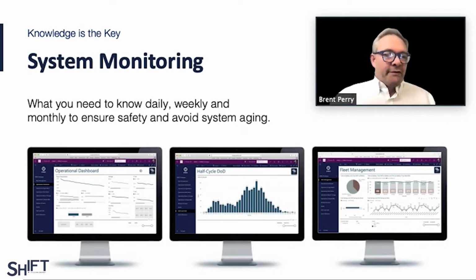We can do that today with a lot of very sophisticated but usable software. In our case, we monitor the cells at the cell level, no matter how large the system is, and it's that management at the cell level that effectively allows us to proactively prevent fire from occurring. This management system, though, has to be enabled to be operating continuously. You may not be using the energy storage, you may have turned it off, but because a lithium cell is a chemical reaction and it's an organic process, it's never off. And your battery management system has to be active and up 100% of the time, and able to communicate with the system's owners to ensure that they have full understanding of how the batteries are operating.